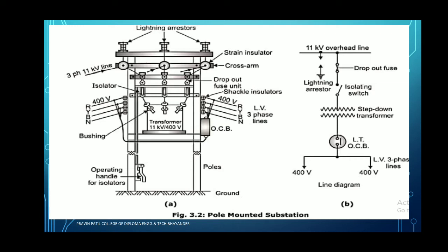Next we have to see the image of that. The image contains a lightning arrestor, strain insulator, cross arm and fuse unit. Here also the 11 kV line is the incoming line. That incoming line is directly fed to the step down transformer. Then that step down transformer converts 11 kV into 440 volt, that is the step down voltage, or into 400 volt, with the help of the step down transformer.